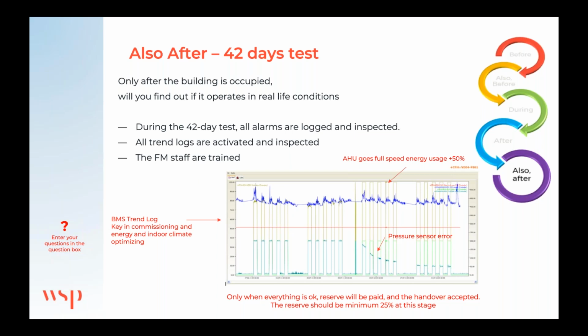I brought with me this example, and this is a trend log for a building where you can see the pressure sensor in the middle here suddenly drops. It suddenly goes down during a number of days. Each of these is a day, you can see 5 days and 5 days. And when this pressure sensor goes down, the air handling units drive up the speed of the fans, and that actually increases your energy usage here by 50%.